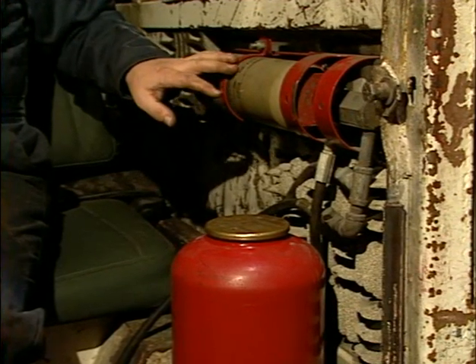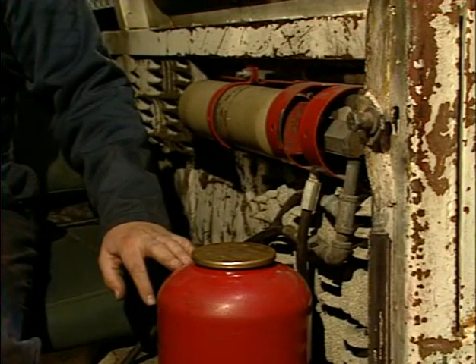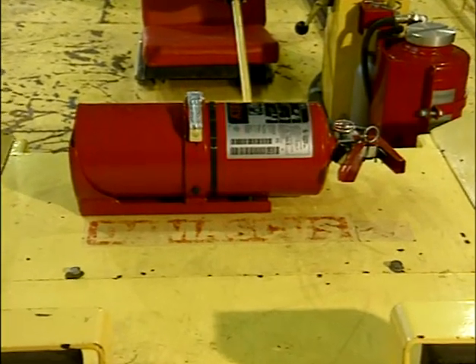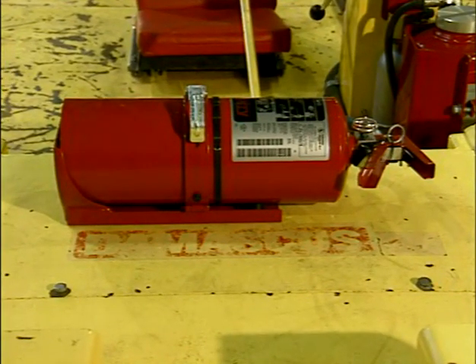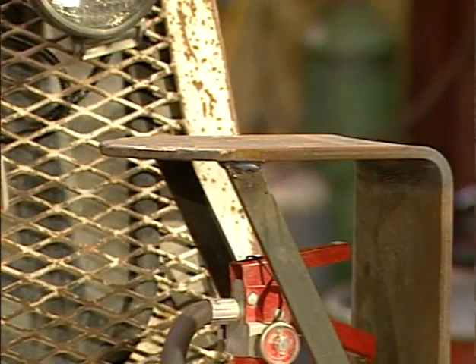This canister and pressure cylinder are protected because they are mounted in the cab. Each diesel powered machine will be required to have at least one 10A-60BC fire extinguisher. The fire extinguisher must be located within easy reach of the operator and must be protected from damage.